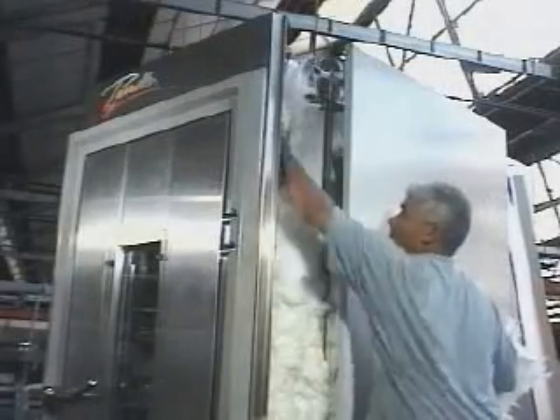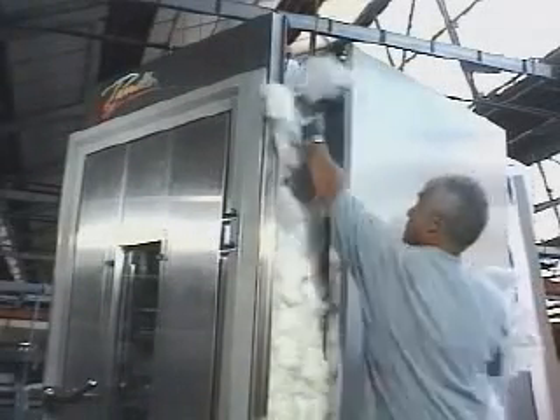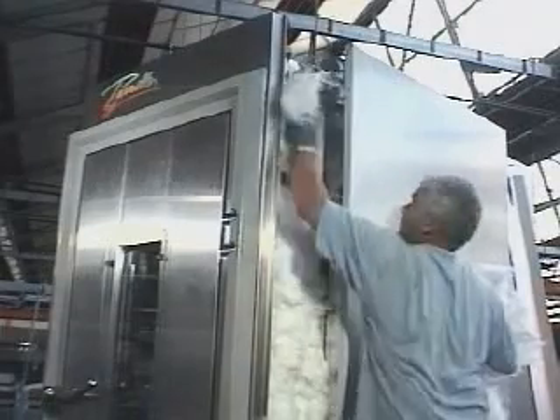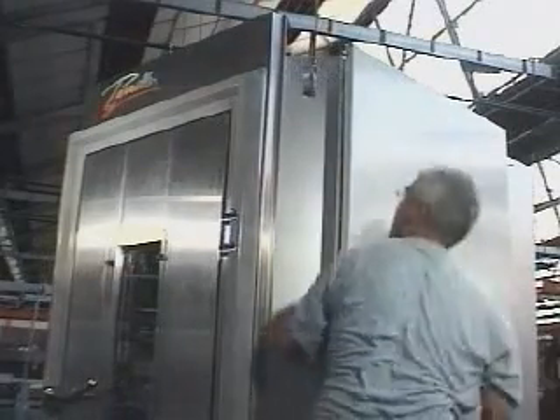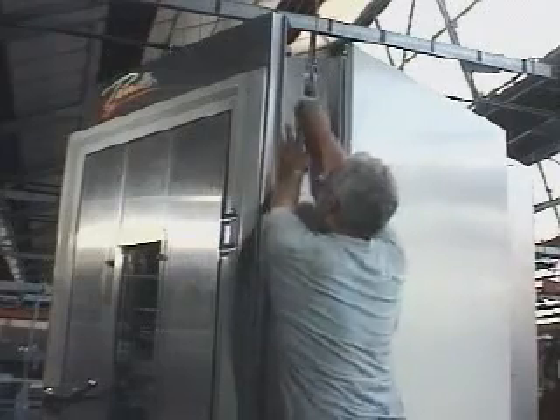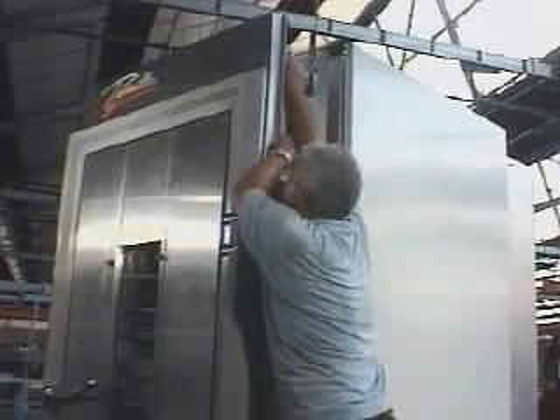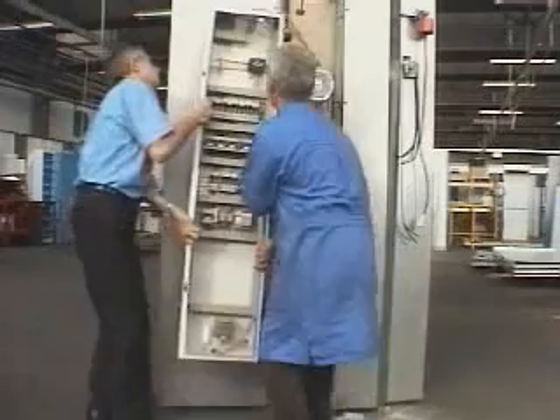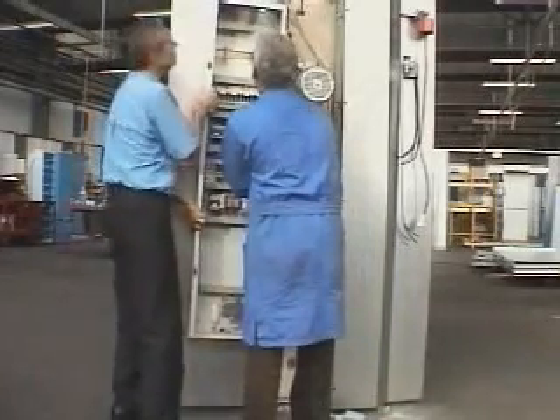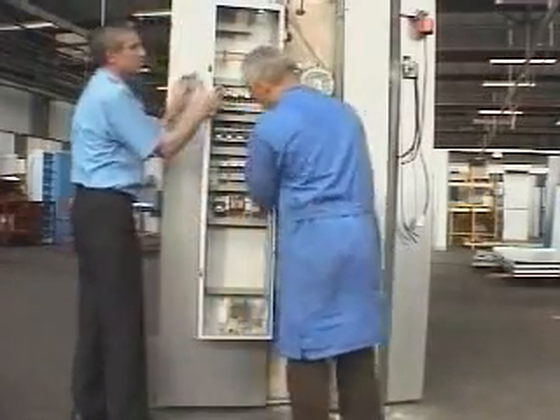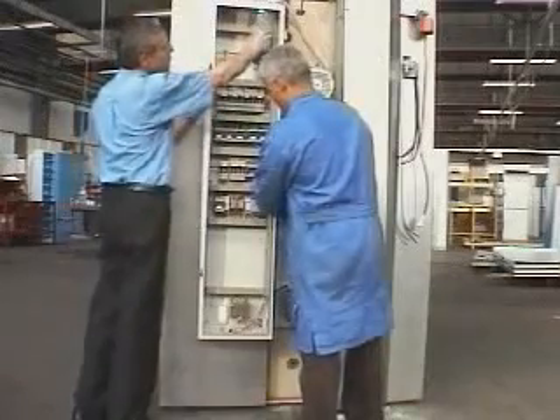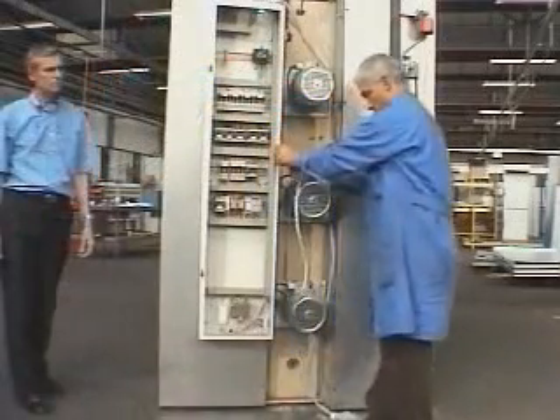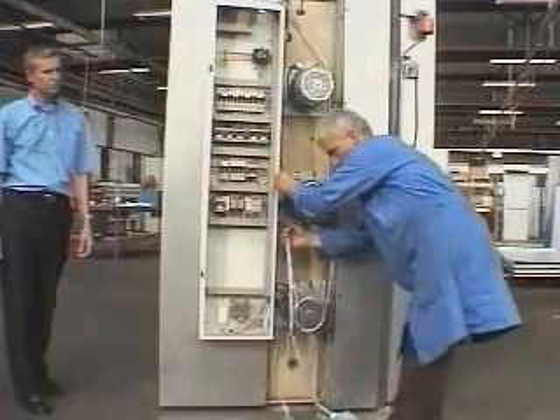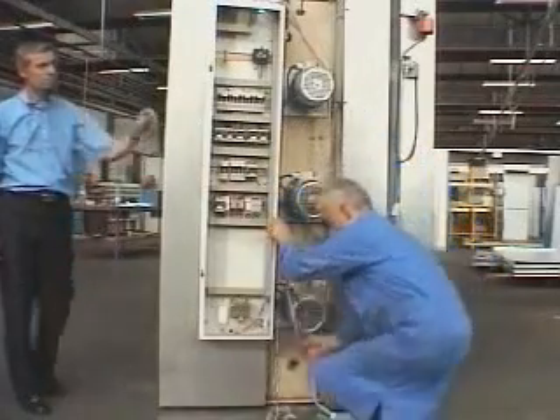Line the angles with glass wool. Assemble by click-in on the panel side and by screws on the door unit side. Finalize top insulation. Place and fix the electrical cabinet with 6 nuts at the base. Stick an adhesive sponge seal to each side of the front panel.